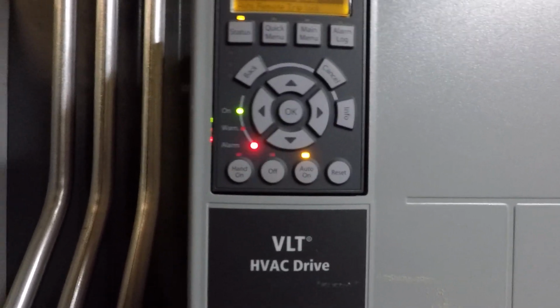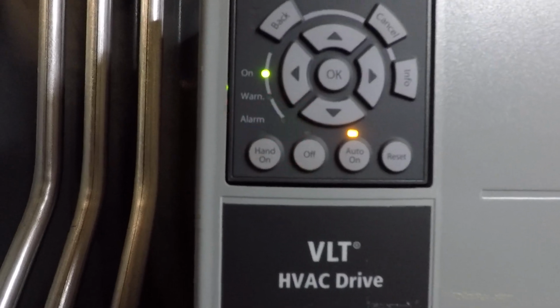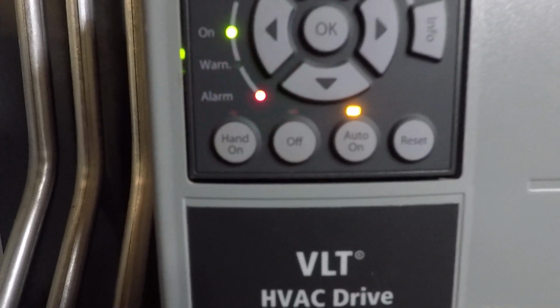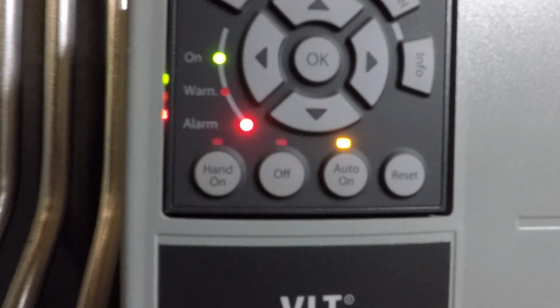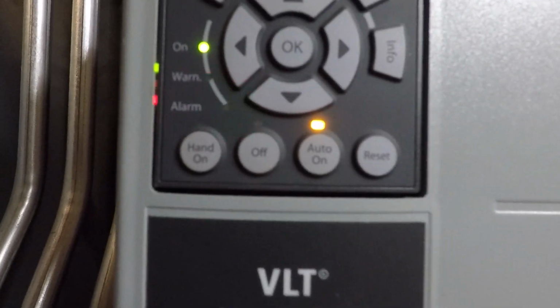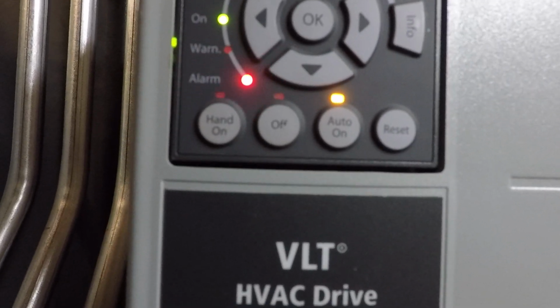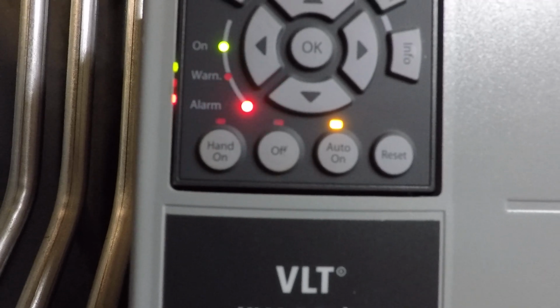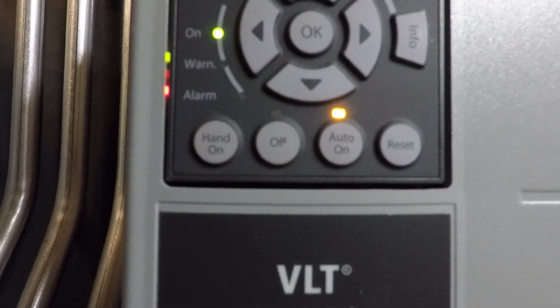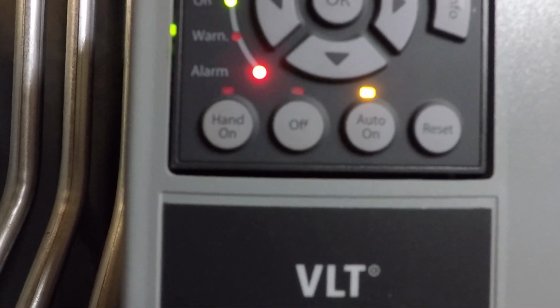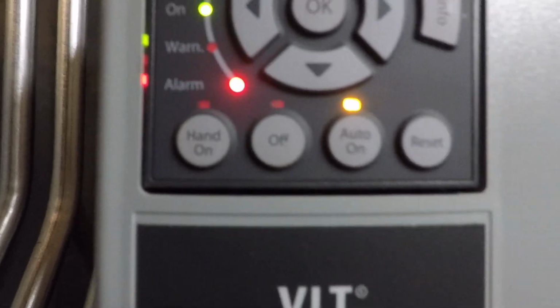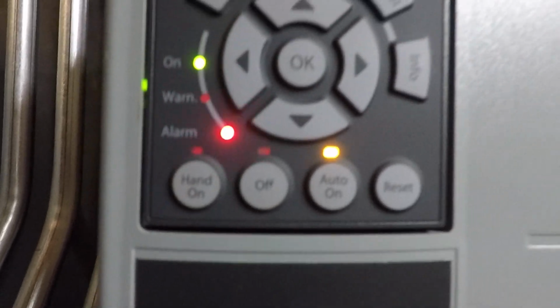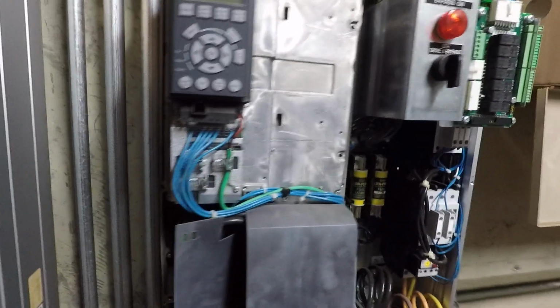If you want manual control, you would put it in hand, and I don't know if that's focusing there. Put it in hand, and you have to use manual speed control, and that will start the drive. When you hit hand, it will turn it on. So you can't separate the speed signal from the start command whatsoever. Now, over here we have the same thing.